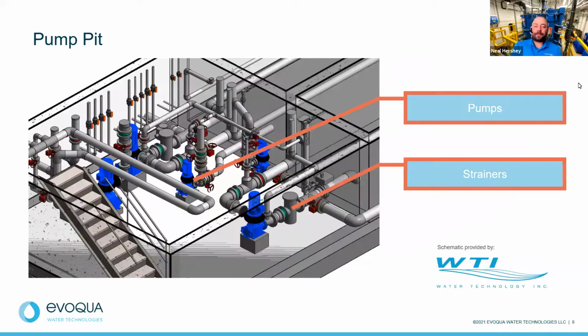So after the surge tank, right on the other side of the wall is generally a pump pit, where all your pumps and strainers and everything comes through from the concrete wall and hits that pump, and then it's the start of your circulation system inside the enclosed mechanical space. Generally the pump pit is down below grade. Most pumps require flooded suction, so they're going to be the lowest point in your mechanical system. A strainer will be on the suction side of the pump to provide a layer of protection. So any debris that's come through your surge tank is going to get caught in that strainer, and then protect the pump and everything downstream.